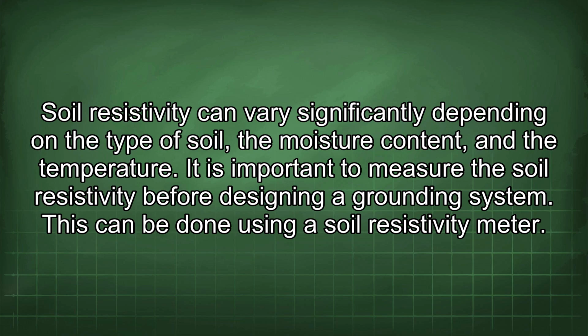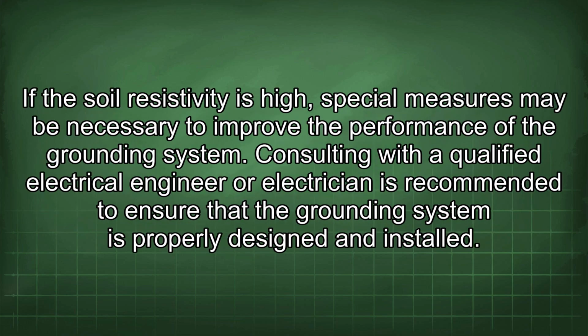It is important to measure the soil resistivity before designing a grounding system. This can be done using a soil resistivity meter. If the soil resistivity is high, special measures may be necessary to improve the performance of the grounding system. Consulting with a qualified electrical engineer or electrician is recommended to ensure that the grounding system is properly designed and installed.